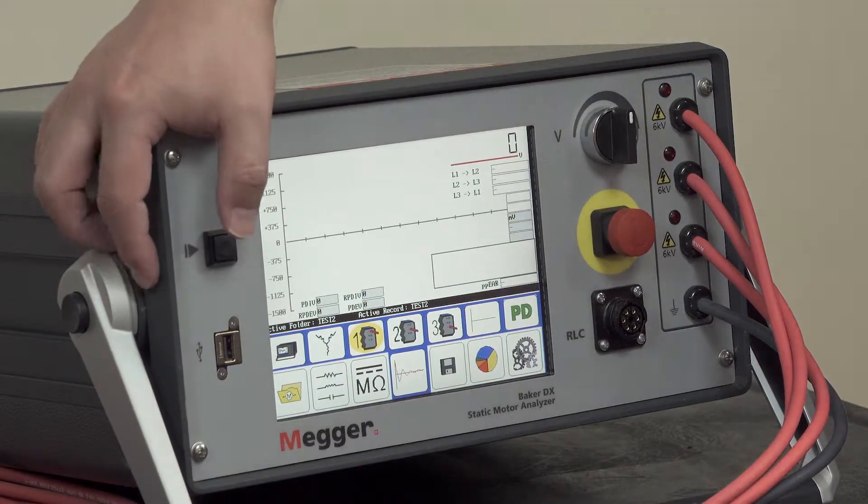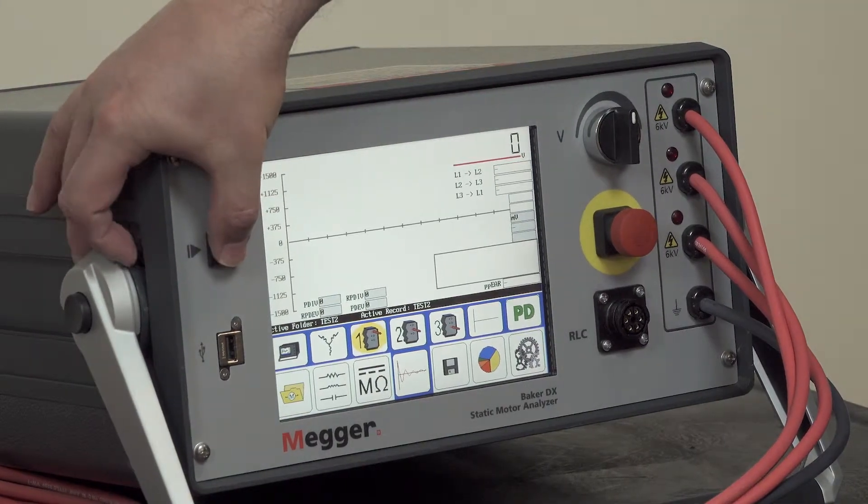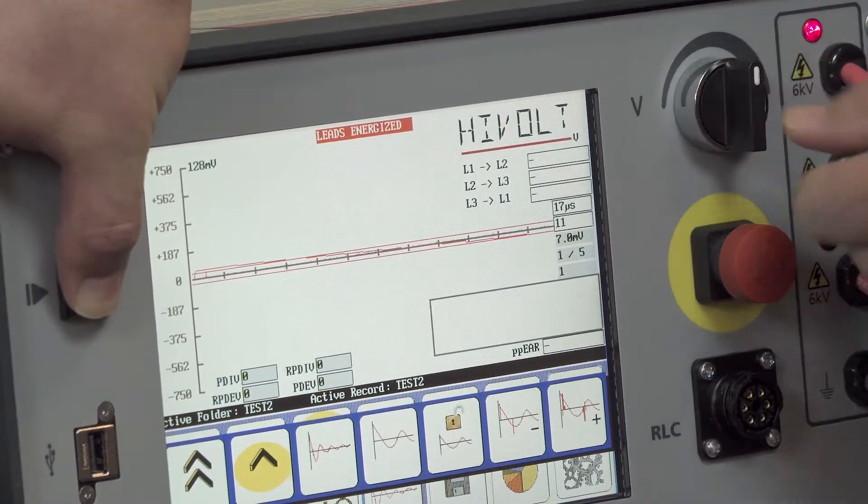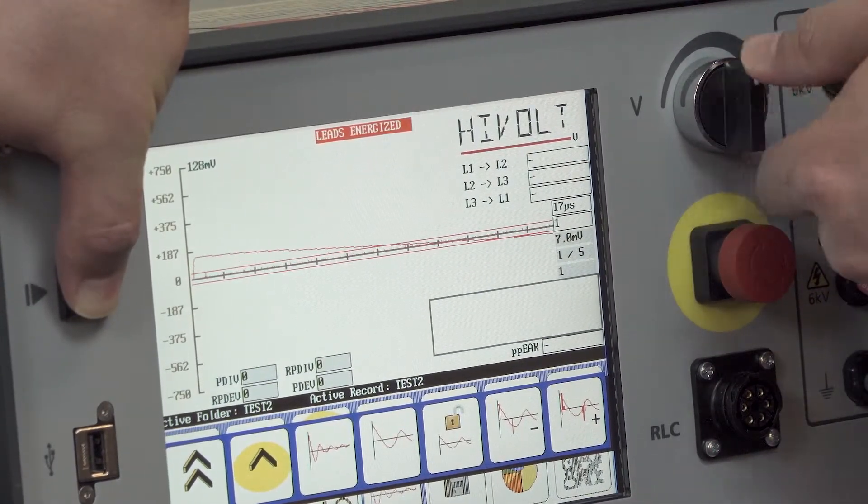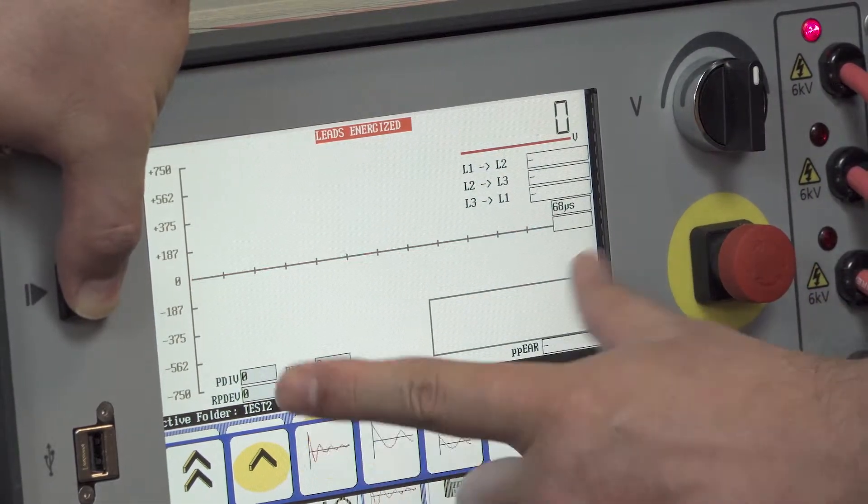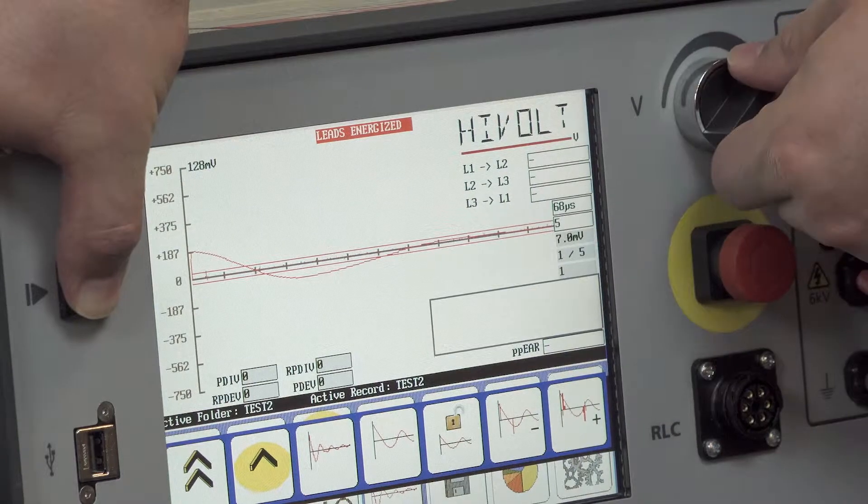And to commence the surge test, we simply press and hold the push to test button, ramping using the voltage control knob to the desired test voltage, ensuring that we scale the waveform to take up a good portion of the screen.